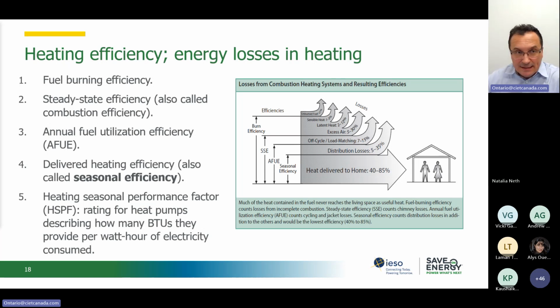But let's finish this discussion here. I've added here the heating seasonal performance factor, which is going to be further discussed in the heat pumps section, because this is a way for us to define the efficiency of the heat pump. We can't really call it efficiency, and I'll explain why, but this is basically accounting for the useful output, basically the BTUs of heating that we provide to the building for each watt-hour of electricity input into our equipment, into our heat pump.